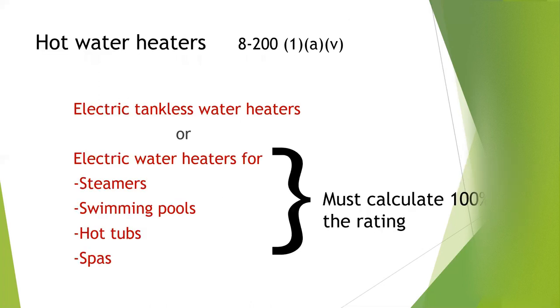For hot water heaters — Rule 8-200 1-A-5 — electric tankless water heaters, or electric water heaters for steamers, pools, hot tubs, and spas are all calculated at 100%. You have to think that thing can turn on at any time and has to keep up with demand — on-demand water heaters, like the Navien system. That's why you take them at 100%.